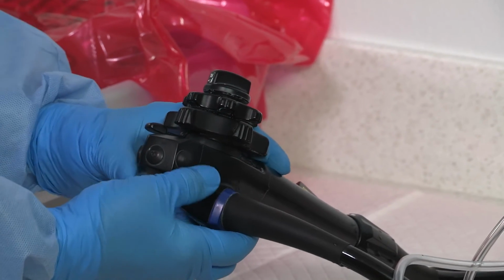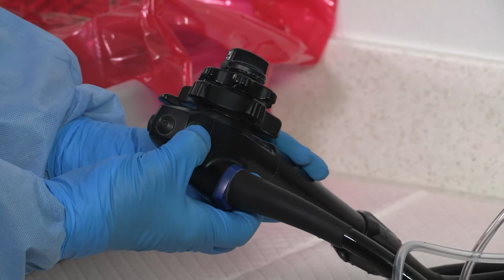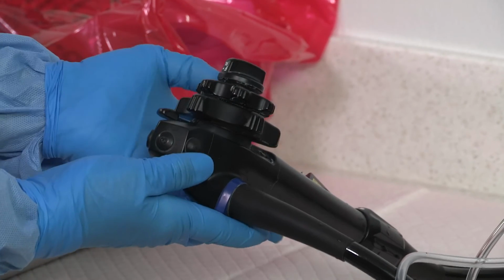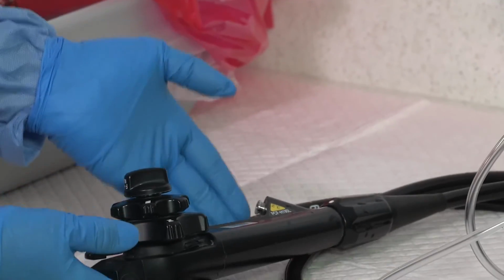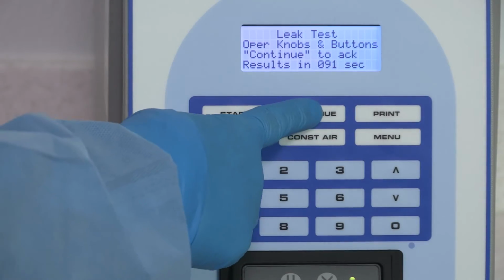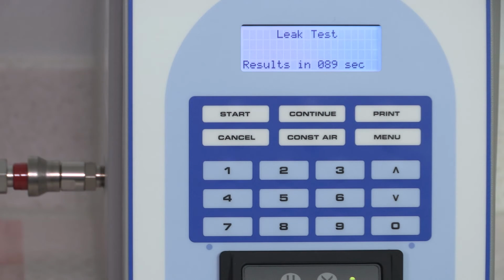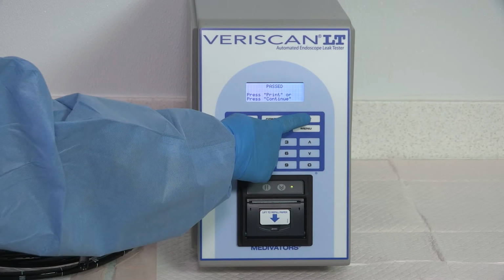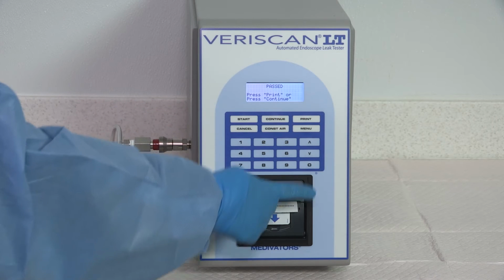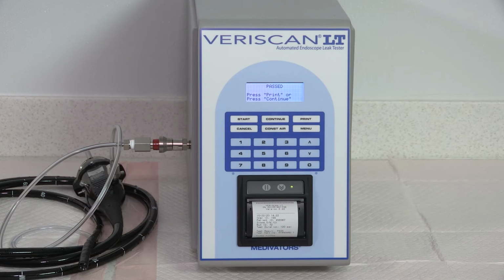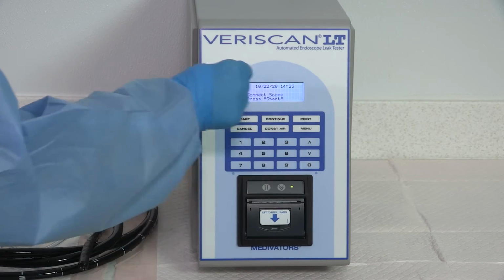These areas of an endoscope are common fluid invasion problem spots that can be accurately leak tested only when all the endoscope's knobs and switches are exercised, and then press Continue. When the leak test completes, an audible tone sounds and the screen displays the pass or fail test result. If a pass result is displayed, either press Print to print the results or Continue to start a new endoscope leak test. Tear the printout off by pulling up against the serrated edge.